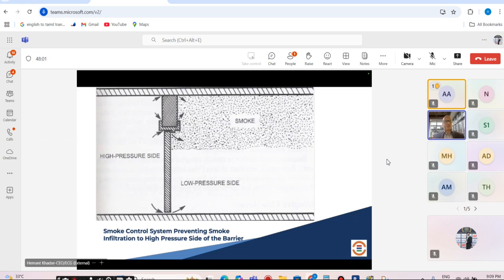Fundamentally, why is pressurization going to be effective? Because we all know that principally smoke always transfers from high pressure to low pressure. It is not the other way around. So when you build that differential pressure, supposing you are pressurizing the staircase, it is built with a high pressure with the jet fans or extraction fans, mechanical fans. The connected lobby will have a low pressure, ensuring the lobby smoke will not enter into the staircase, because we want to protect the staircase first, being an exit route.